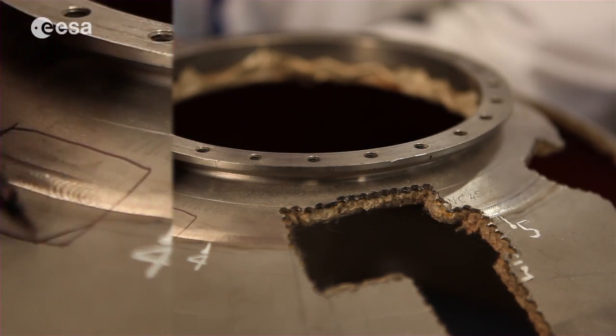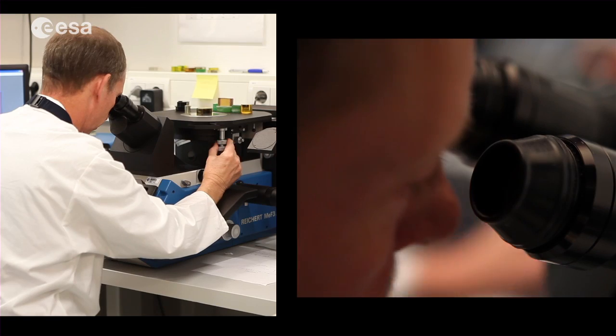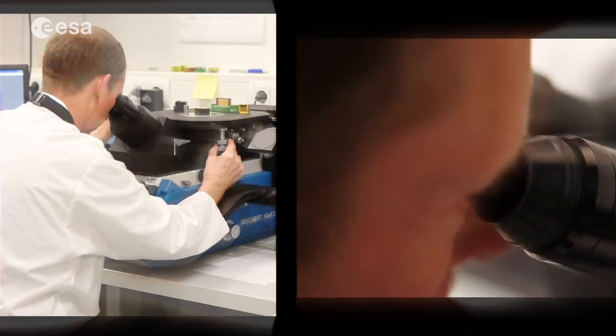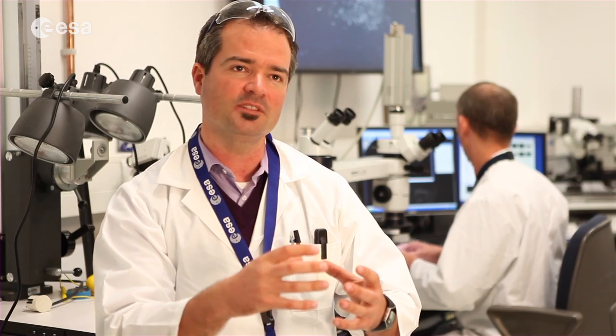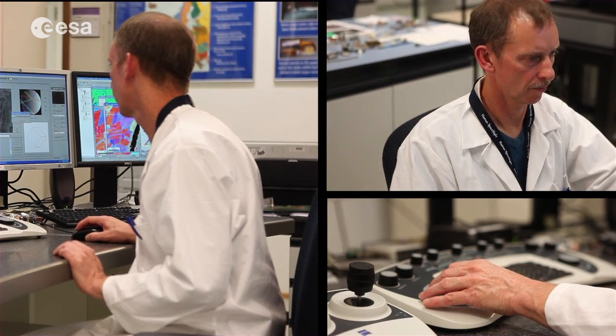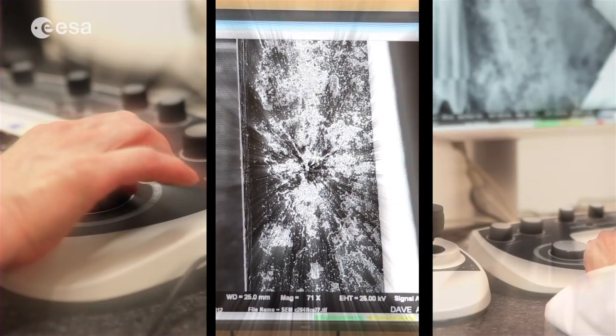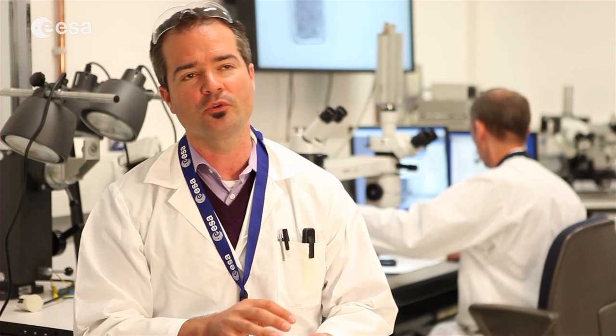We cut pieces from the tank. Then we made a visual inspection. Optical examination revealed a discolored surface, which is very unusual for a welded sample. From this point, we could go into more detail in the scanning electron microscope, looking at the fractured surface to really find the fracture mode and the fracture path through the material.